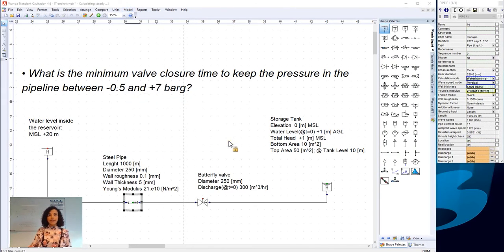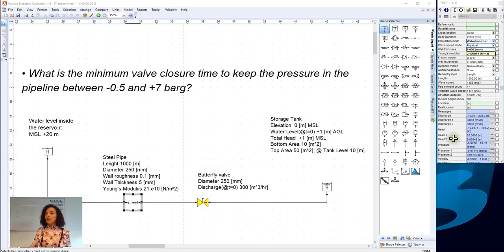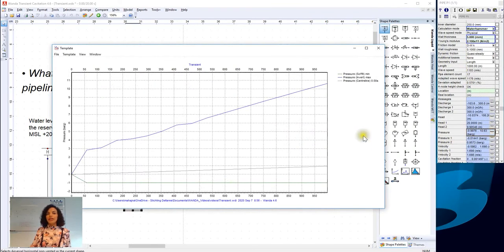Now, Wanda is calculating steady-state results, and then it calculates transient. As we are interested in looking at the pressure in the pipeline system, we select the pipe component, and we look at the pressure values in the pipeline system. And as we can see, the pressure is exceeding our allowable pressure criteria. It is going above 7 bar gauge and reaching minus 1 bar gauge.